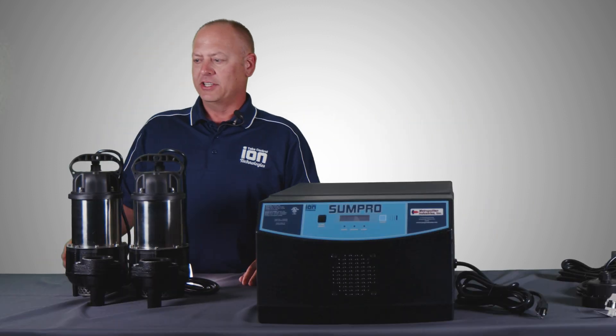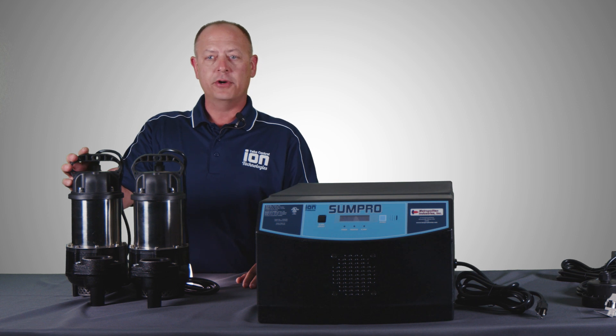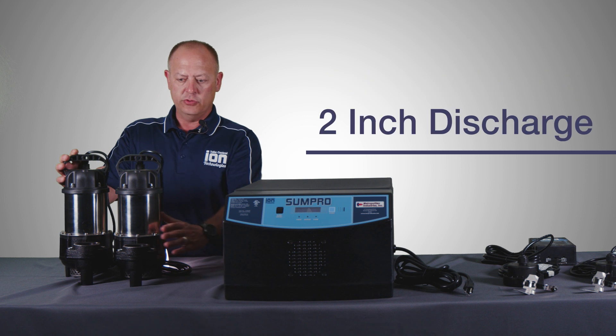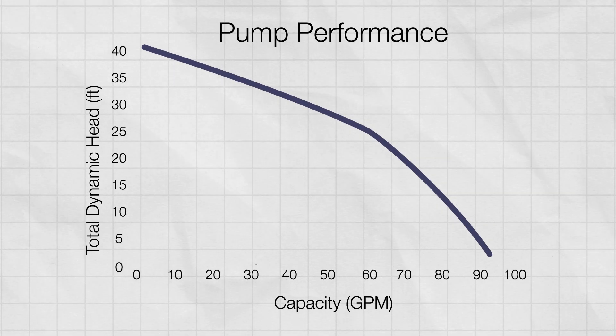Last but not least in the SumPro Platinum package, we have two three-quarter horsepower BA75 sump pumps. These are stainless steel cast iron. They have a two-inch discharge and capabilities of pumping up to 86 gallons a minute at 10 feet of head.